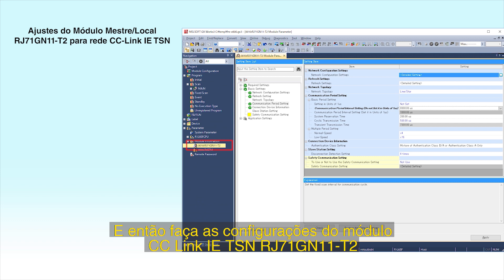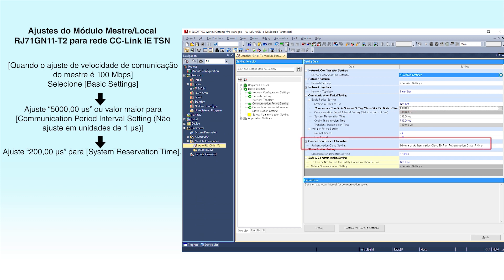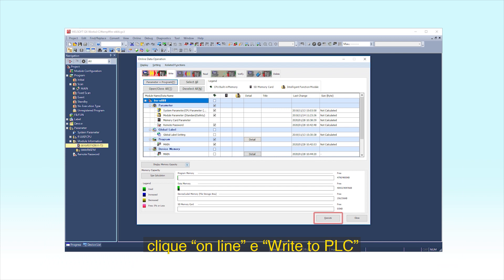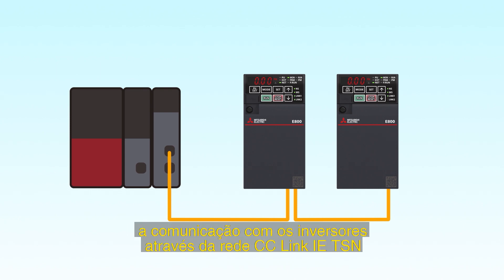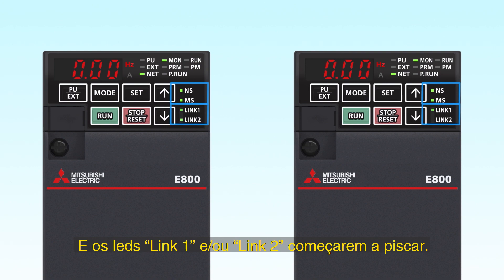Make settings for the CC-Link IE-TSN Master Local Module RJ71GN11-T2. This completes the setting process. To initiate writing to the programmable controller, click Online and then Write to PLC, then click the Execute button. After the writing has been done, check the inverter's LEDs. CC-Link IE-TSN communication has been successfully established when the NS and MS LEDs constantly display green and the Link 1 or Link 2 LED is flashing green.